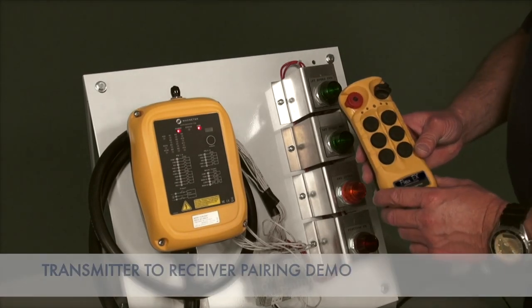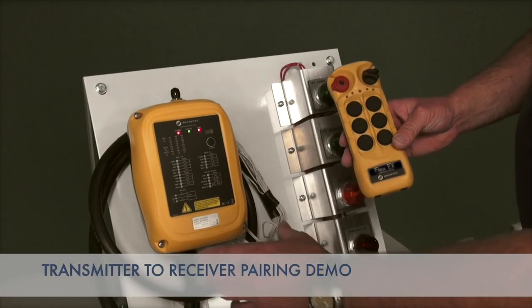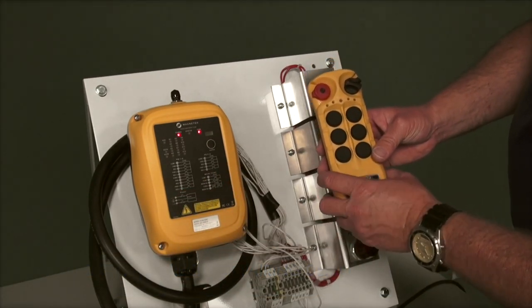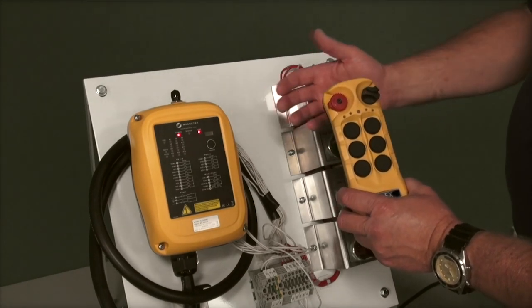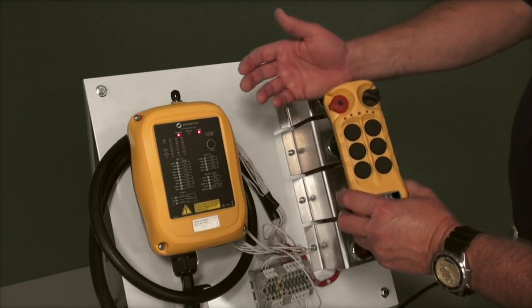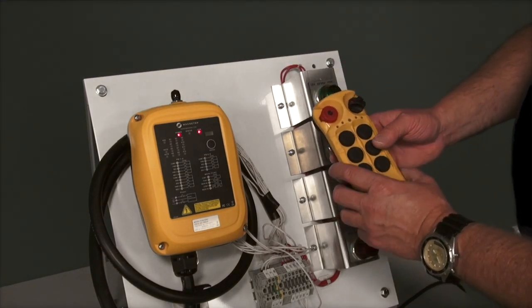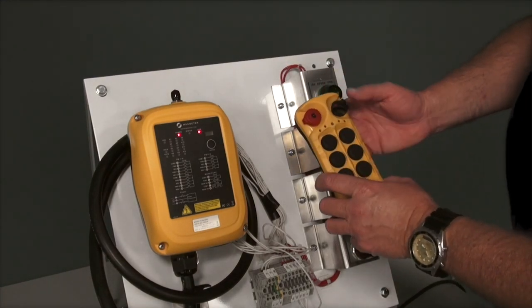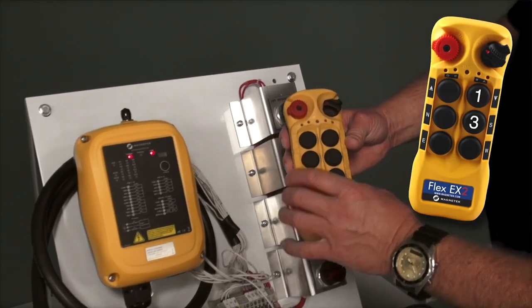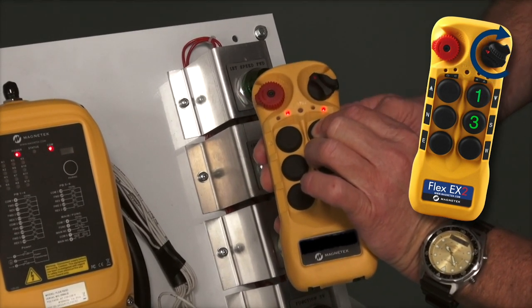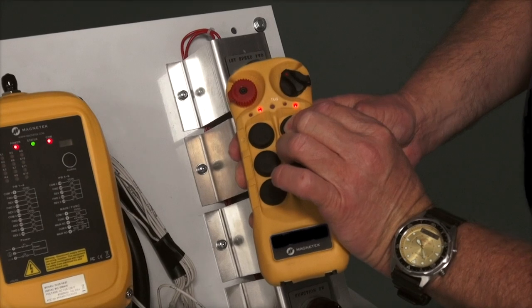We're going to demonstrate pairing between a Flex EX2 receiver and a Flex EX2 transmitter. This is accomplished by an RF signal being sent from the receiver to the transmitter. To start, we make sure the E-stop button is out. We're going to depress buttons number 1 and 3 on the transmitter. I'm going to turn the transmitter on.